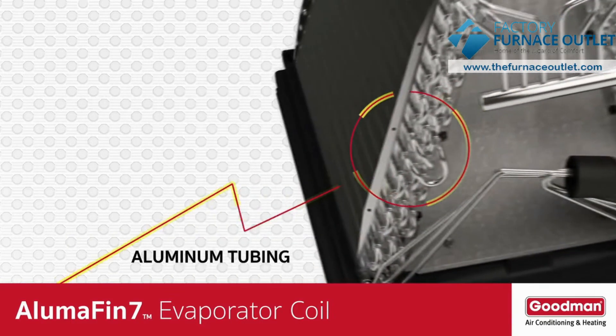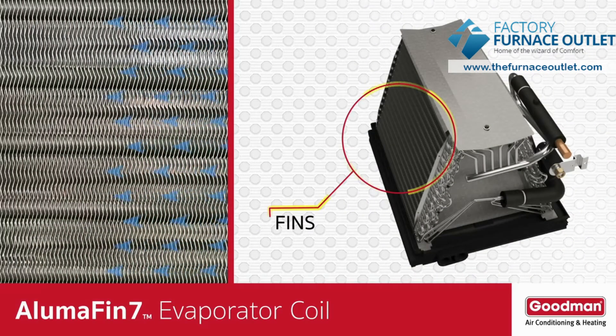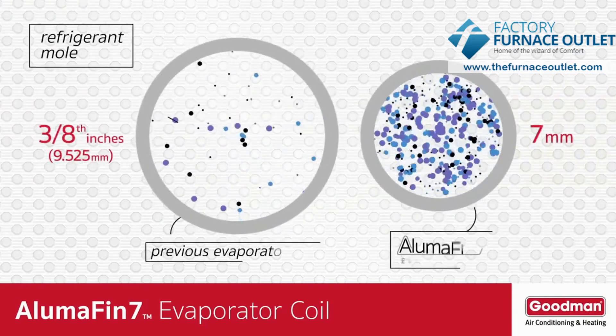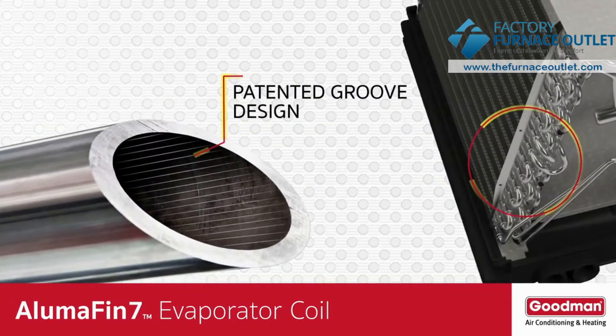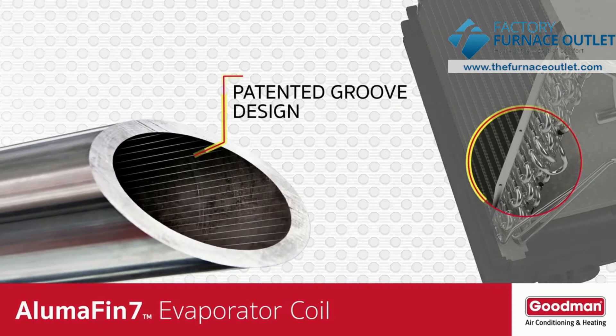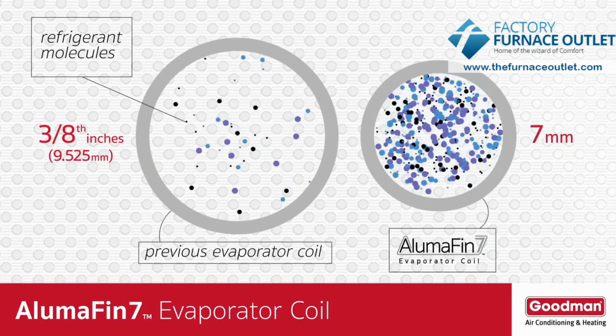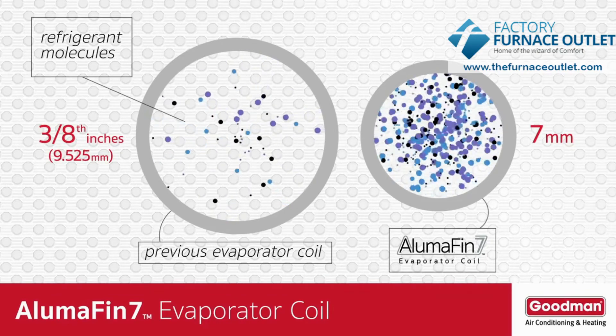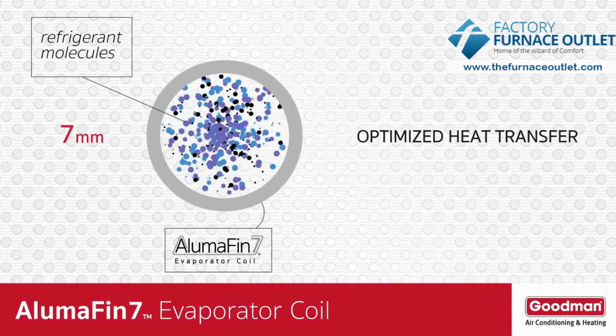The AlumaFin7 evaporator coil tubing is just 7 millimeters in size. These small tubes carry the cold refrigerant across the fins, which is where the condensation or water vapor removal process occurs. The tube size is important because the smaller the tubing, the more efficient the heat transfer process. The inside of the tubing contains grooves that create turbulence in the refrigerant as it passes through. This bouncing effect gives the refrigerant molecules more time to come in contact with the outside of the tubing, determining the efficiency and optimization of the heat transfer process.